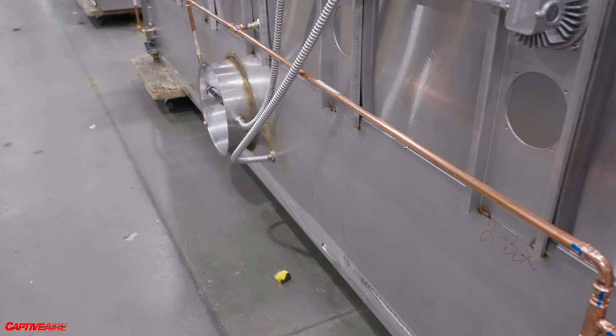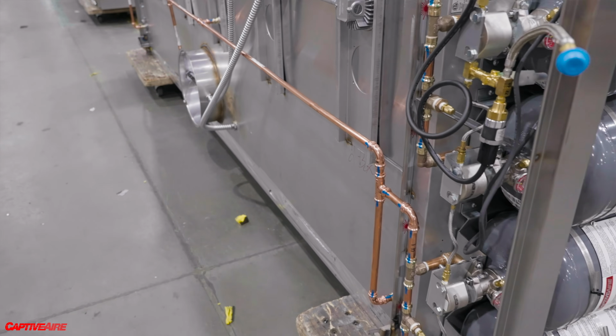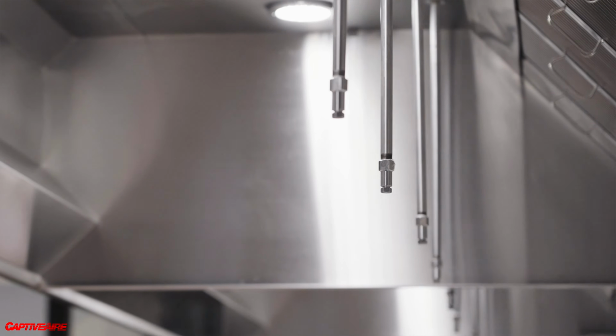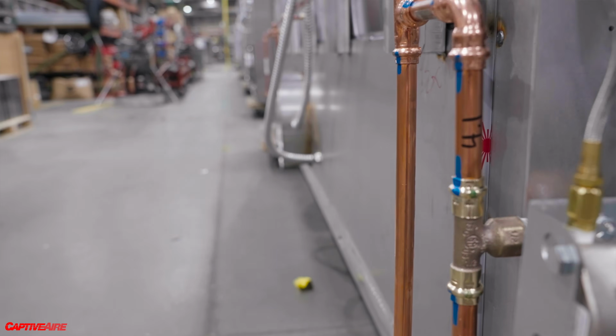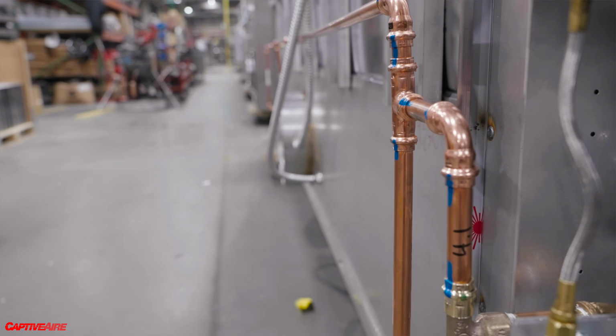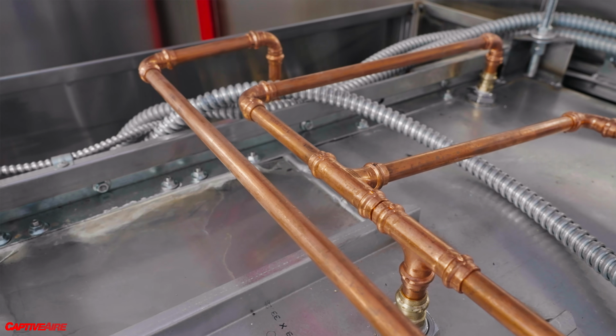You don't have unlimited pressure, so you can't have an unlimited amount of piping in the system, or an unlimited number of nozzles. Every foot of pipe and every elbow adds an associated pressure drop to the system, which reduces how much power you have left at the end of the distribution line.